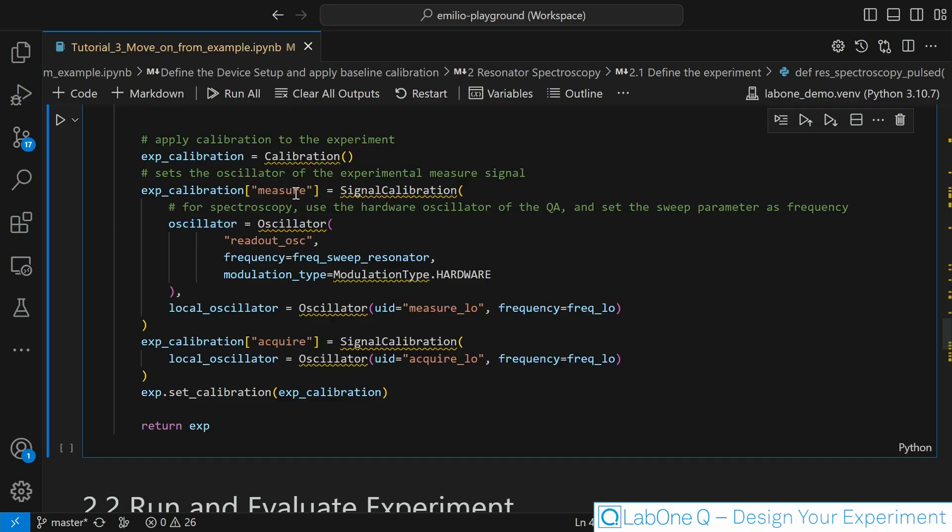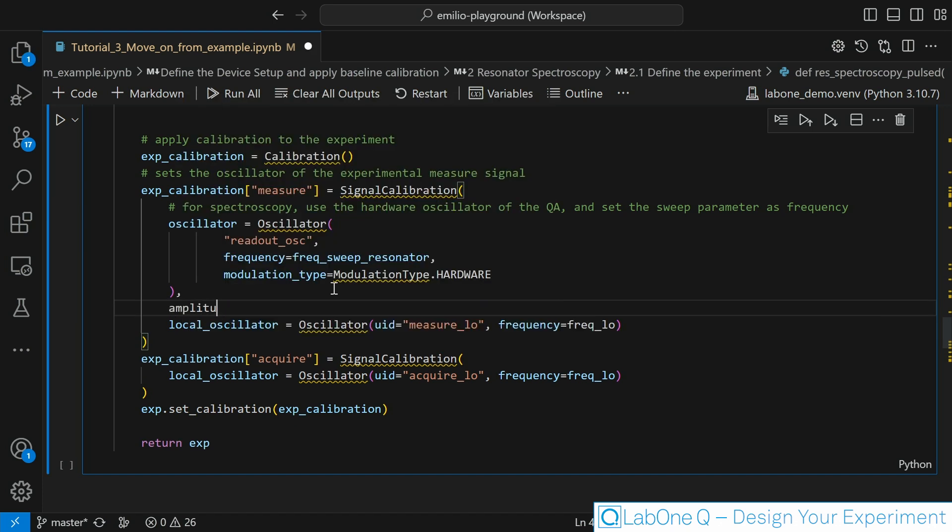Now let's go to our calibration and specifically to our experimental signal measure, which is what is sending the RF pulse to the cavity. And we just need to use one more keyword amplitude, and we pass our power sweep resonator to it. And we are done. I changed three lines of code that I transformed this experiment from a 1D sweep to a 2D sweep that is sweeping frequency and power at the same time. Let's see how it works when we are actually running it.